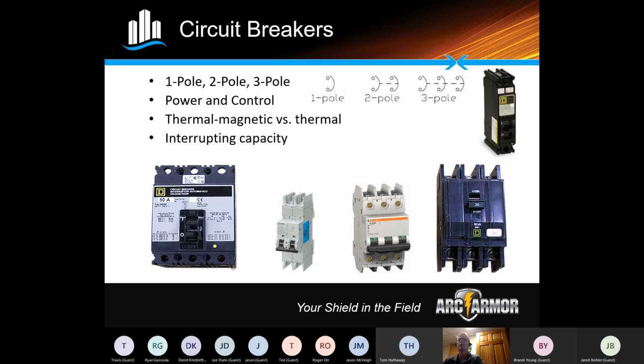So what the manufacturers have done is they've taken breakers and starters and married those together, and then got formalized testing through the agencies to meet certain AIC interrupting ratings. So you're going to hear those terms. I don't expect you to understand or remember all the items we just talked about here, but in the back of your mind, if you hear SCCR, that means how that panel, or an assembly within the panel, is set up, and interrupting capacity is more related to just components. I know that was probably a lot, but I just wanted to throw that out there. Questions on interrupting capacity and SCCR ratings?